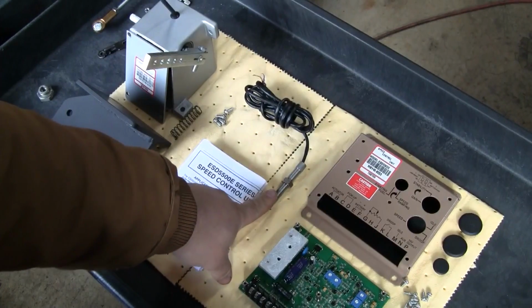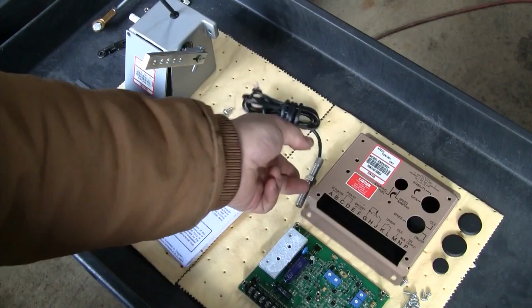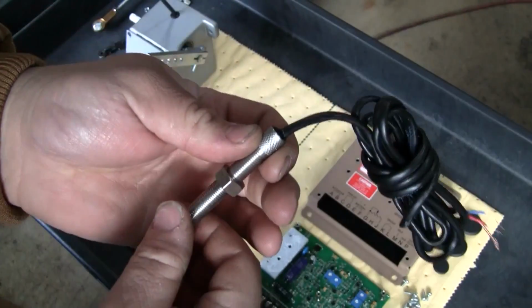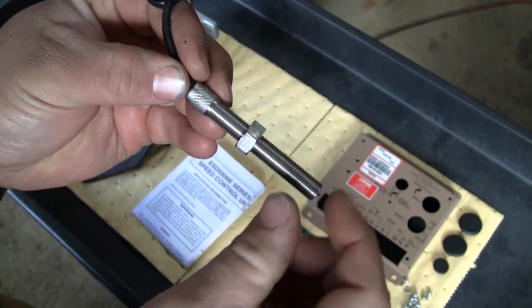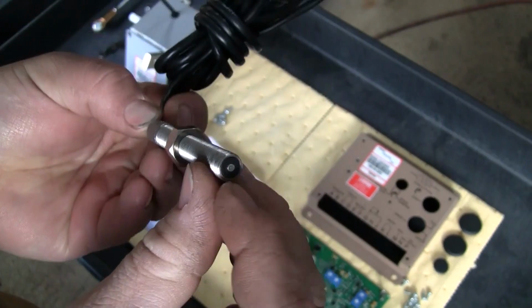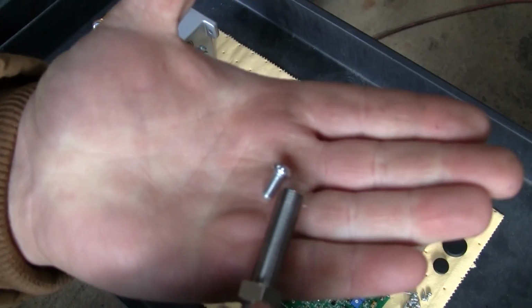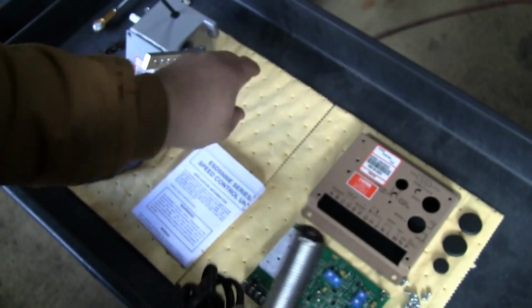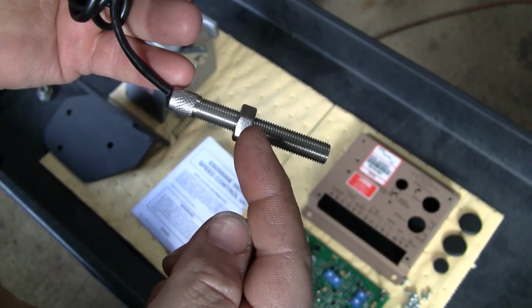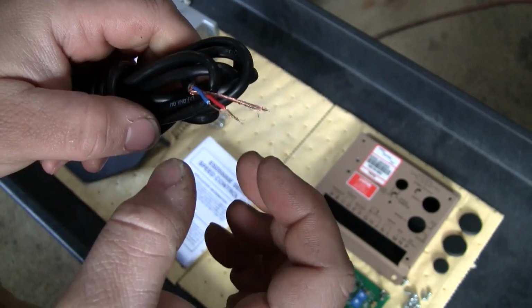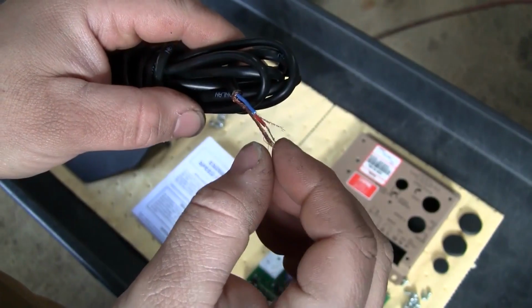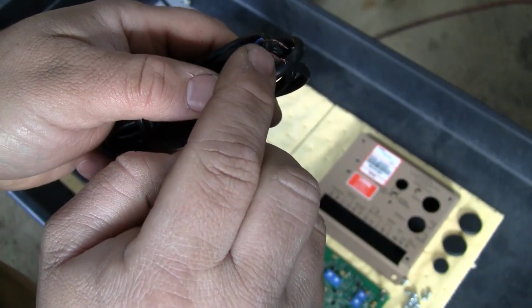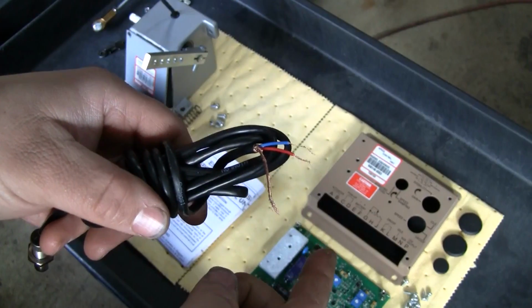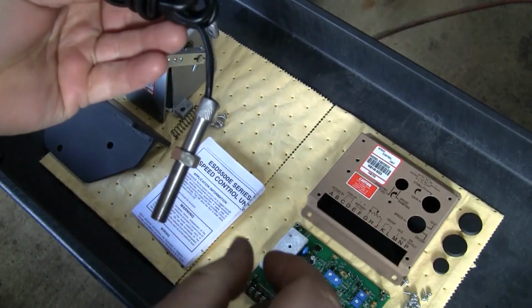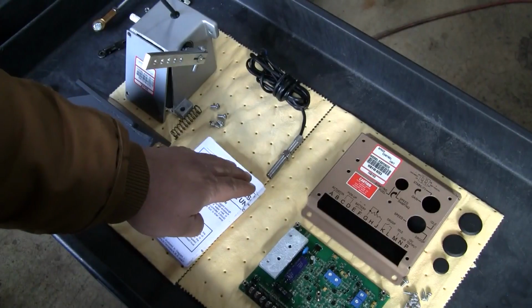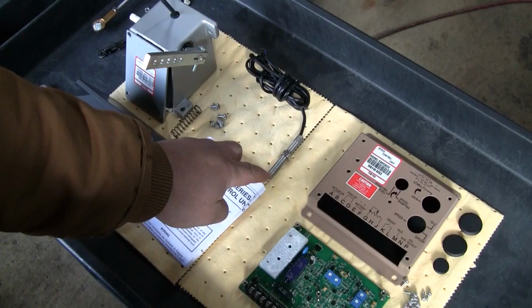It comes with the magnetic pickup, sometimes called a Hall effect sensor. Unlike a typical Hall effect sensor which has a switching device, this is just a coil of wire with a little magnet in the center. There's no switching action happening here. It generates an AC signal on the two wires, blue and red, while the other is a shield. The blue and red generate an AC signal across there, which the controller analyzes and compares to whatever your set point is. That AC signal is generated by the individual flywheel teeth passing very closely to the tip of that sensor.